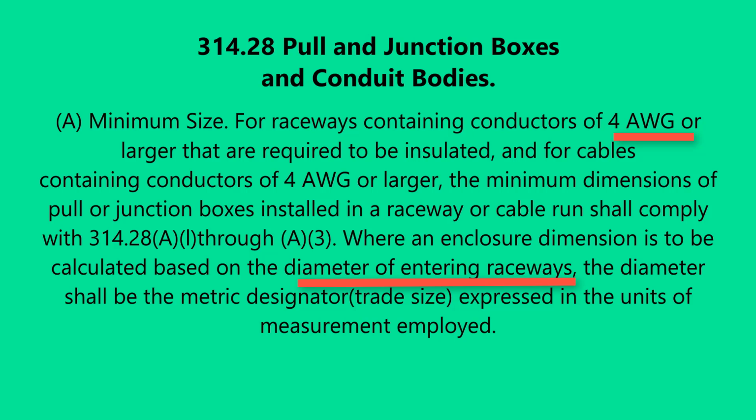Where an enclosure dimension is to be calculated based on the diameter of entering raceways, the diameter shall be the metric designator, trade size, expressed in the units of measurement employed. This states that the box size is determined by the conduit entering the box.